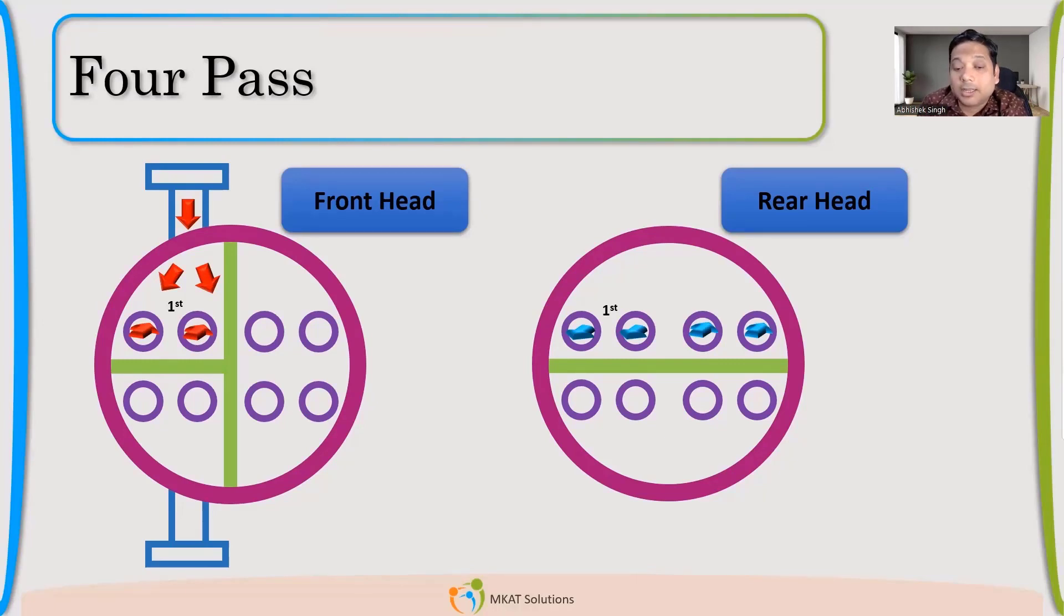Now it will enter in the two other available tubes in the rear side. It will come out like this in the front side. So now two passes. Now here, the partition plate arrangement is such that now two tubes are available for entry. So now it will enter in the available tubes and then it will come out on the other side. So this is third pass. Now it will enter in these two available tubes and will come out from the other side. So total four passes.